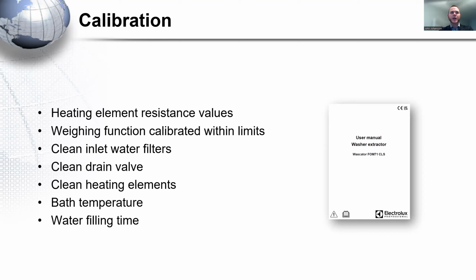It's a little bit trickier. Either you create a device to hang on the door of the machine into the drum with a calibrated temperature device to see the temperature that you reach, or you can use, for instance, a data logger. You will have probably slightly different results if you use a temperature probe hanging on the door or if you use a data logger. Probably not that much, but it's worth considering. Normally, when we calibrate machines from the manufacturer, we use a probe hanging on the door.